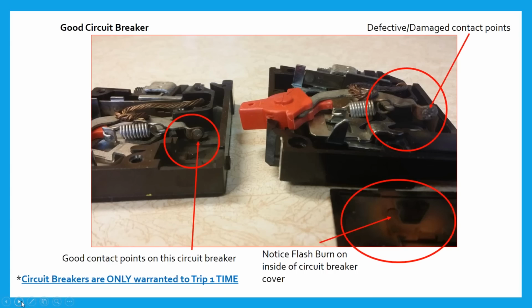But look at the one on the right, notice how it's defective, look at how the contacts are burnt. If the contacts are charred and pitted like that, they're not making a good surface contact. So what happens is all of a sudden we've got wiring that's burning, and now we've got circuit breakers that begin to give it up, and this thing starts compounding on itself.